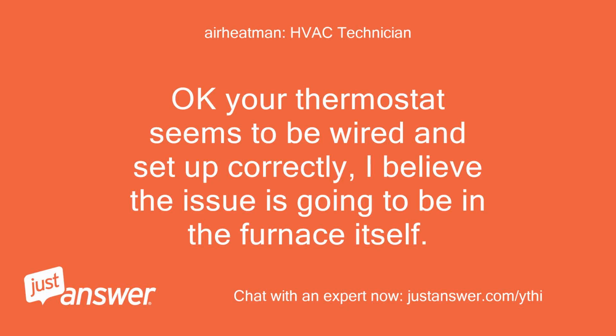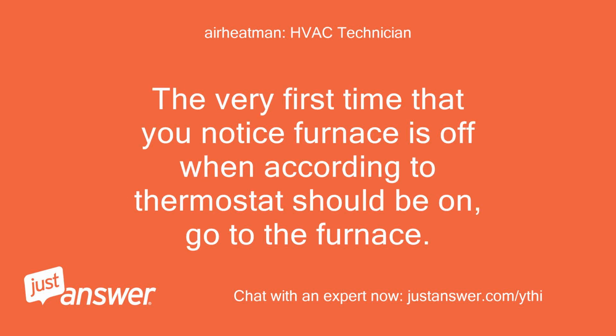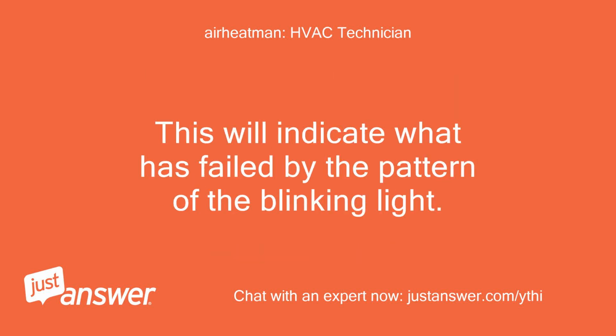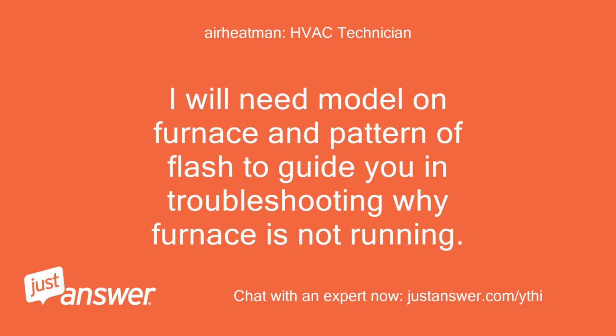Okay, your thermostat seems to be wired and set up correctly. I believe the issue is going to be in the furnace itself. The very first time that you notice furnace is off when according to thermostat should be on, go to the furnace. There should be a small inspection window on blower door. Look inside and see if we have a blinking light on furnace control board. This will indicate what has failed by the pattern of the blinking light. I will need model on furnace and pattern of flash to guide you in troubleshooting why furnace is not running.